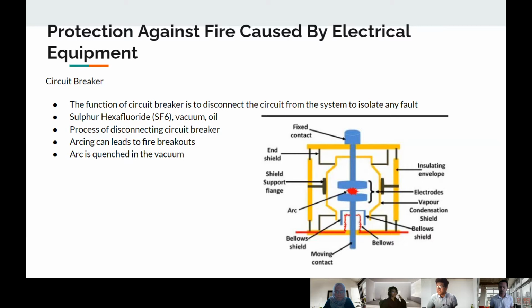Based on the IEE wiring regulation, whenever an arc or spark at high temperature may be emitted in fixed equipment in normal service, one of the requirements is that the equipment should be totally enclosed in arc resistant material, for example a vacuum circuit breaker. There are many types of circuit breaker such as sulphur hexafluoride, oil, and vacuum. Today we're going to talk about the vacuum circuit breaker.